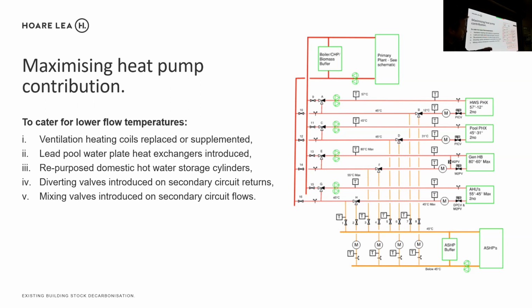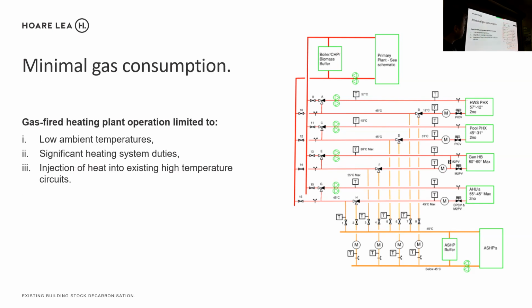We diverted the return circuits through the air source installation so it could do as much work as possible, getting it to as high a temperature as it can within its operating parameters, typically about 45 degrees, to work efficiently. Where necessary, we then injected heat from the boiler circuits through an injection valve or flow circuits. This meant the existing gas-fired boiler installations would only really operate at very low temperatures, during significant heating system demands, or when we needed to inject heat into the existing high temperature circuit.